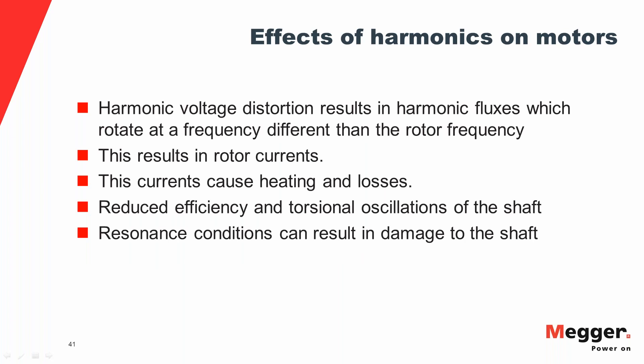Regarding effects of harmonics on motors: harmonic voltages result in harmonic fluxes rotating at frequencies different from the rotor frequency. The interaction between these fluxes and the conductors induces currents that cause heating and losses. Additionally, the interaction between currents and the field results in a pulsating torque, causing oscillations on the shaft. If the frequency of the pulsations matches the natural frequency of the shaft, mechanical resonance can occur, amplifying the oscillations and potentially causing damage to the shaft.